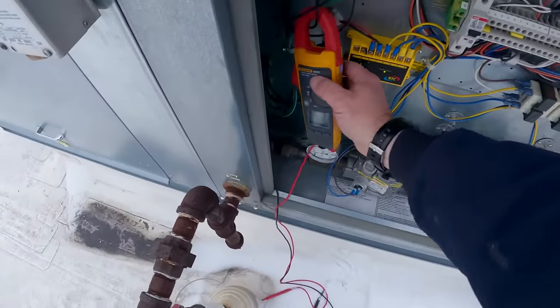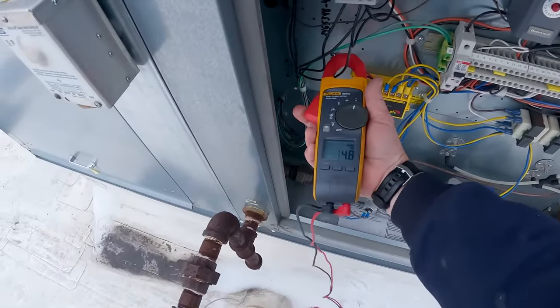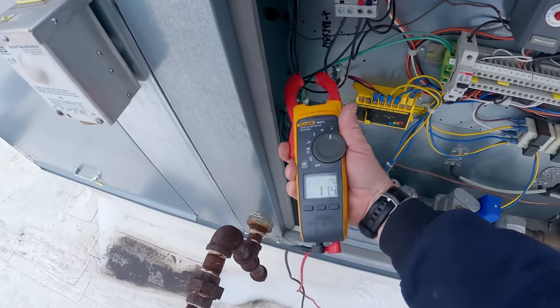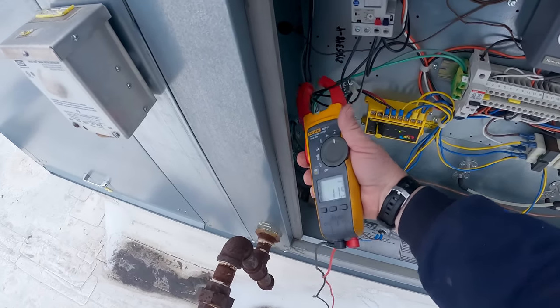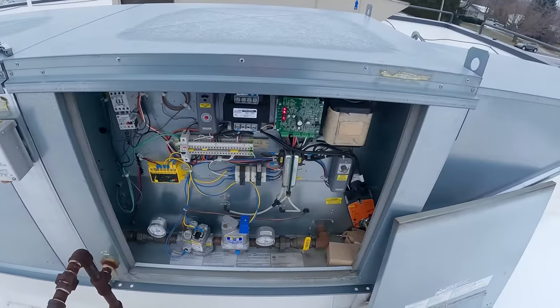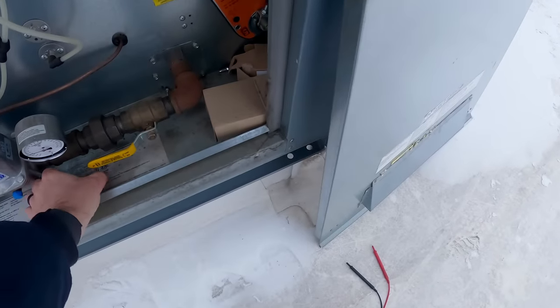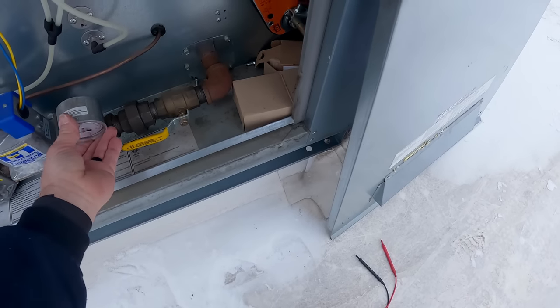Fired off just now — 11 amps, 11, 11.9. Now we could have a problem with the motor not starting every time. At this point I don't know if that's an issue or not.